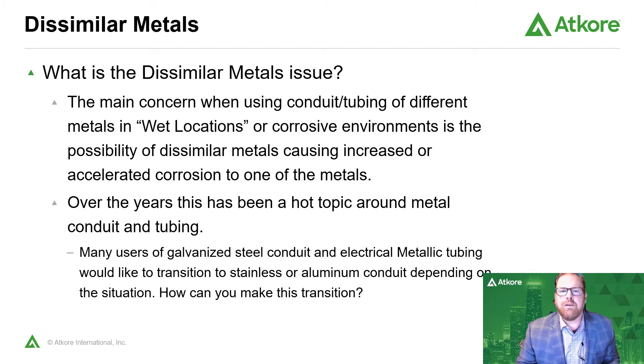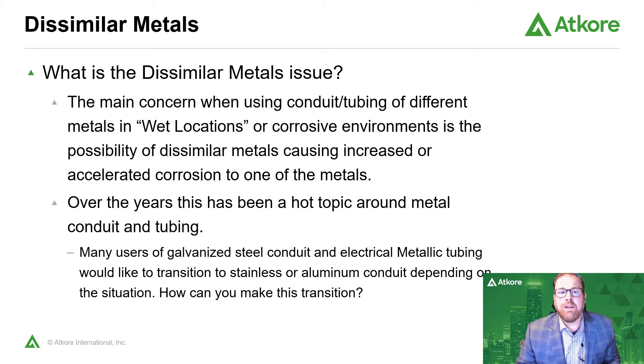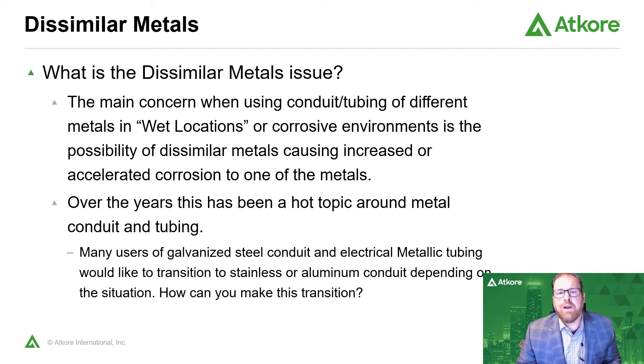So what is the dissimilar metals issue? The main concern when using conduit and tubing of different metals in wet locations or corrosive environments is the possibility of dissimilar metals causing increased or accelerated corrosion to one of these metals. Over the past few years this has become a hot topic around metal conduit and tubing. Many users of our galvanized steel rigid conduit or our galvanized electrical metallic tubing would like to transition to stainless steel conduit or aluminum conduit depending on the situation. How do you make the transition without causing accelerated corrosion, and which types of these metals are allowed to be used together? Those are the topics we'll be discussing today.